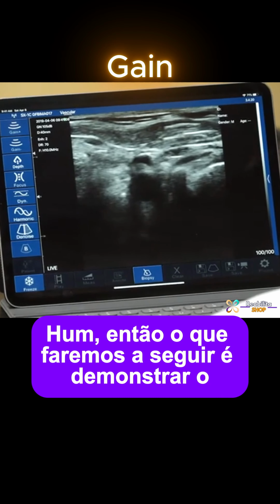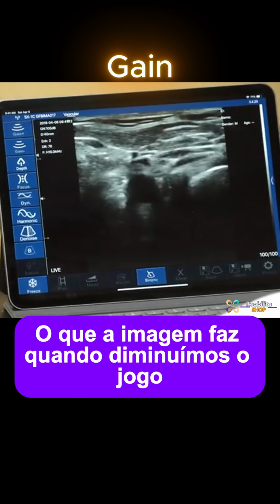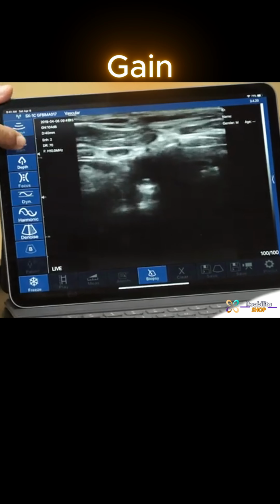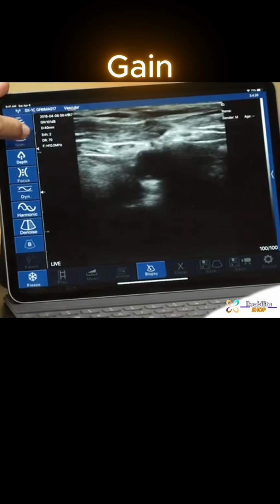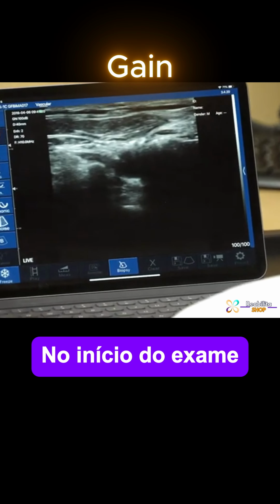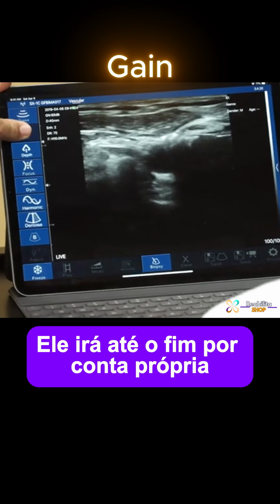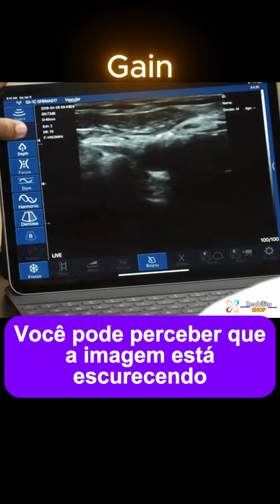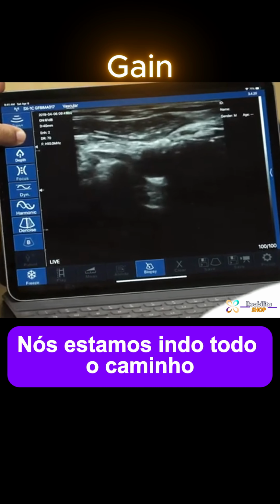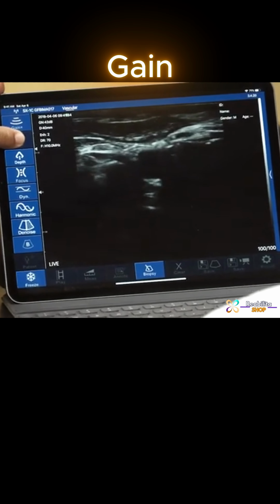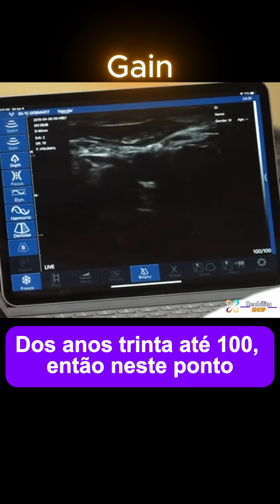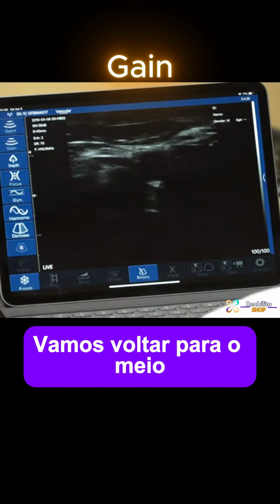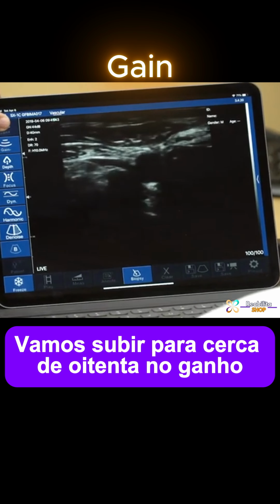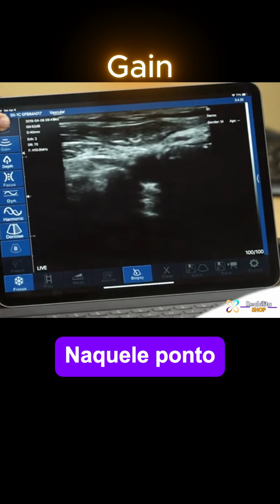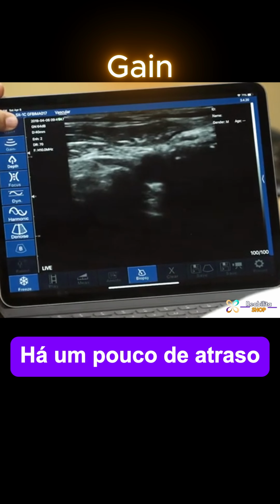So what we'll do next is demonstrate what the image does as we decrease the gain. And we'll go all the way back down to where we were at the beginning of the exam. If you just touch it and hold it, it will go all the way down on its own. You can appreciate that the image is darkening. We are going all the way down. Keep going. That's great. So you can see there's quite a range of variability from the 30s up to 100. So at this point, we're going to go back up to the middle, somewhere around 70 to 80. Let's go up to around 80 on the gain, and we'll do the rest of our exam at that point. There's a little bit of lag.